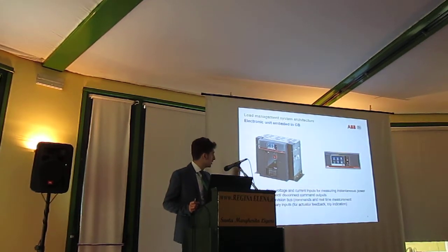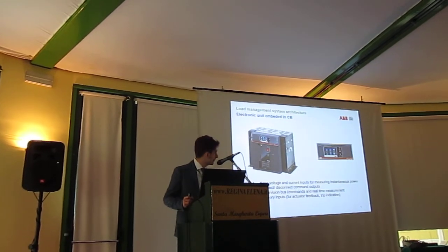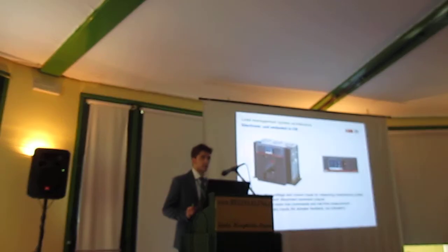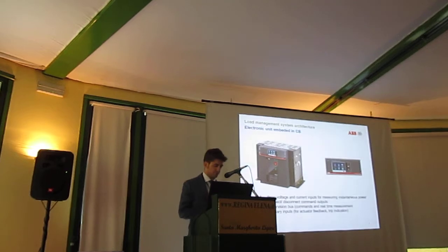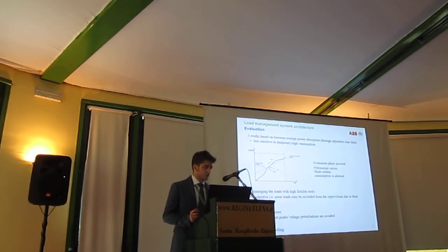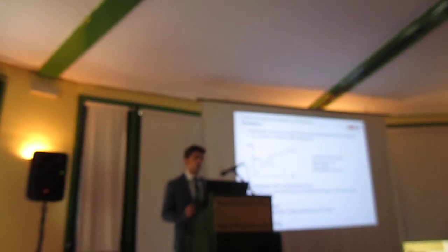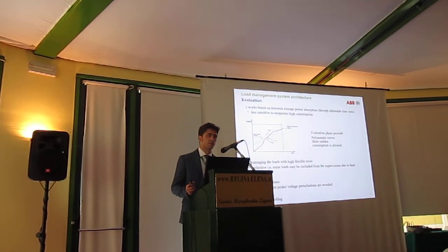Here in this image, you can have a better look at this electronic unit, which from now on I prefer to call the controller. This controller receives 6 signals, 3 for voltages, 3 for currents. This controller is responsible for calculating the downstream load power consumption and taking the proper actions. It also provides some auxiliary inputs.